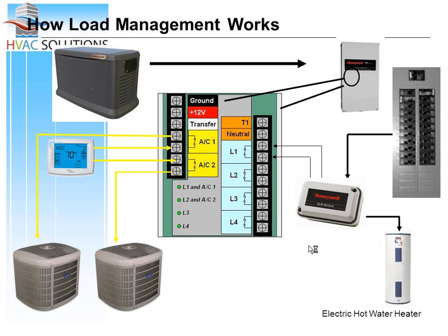So in that case, we wouldn't shed the well pump, even though it's a 240-volt load. We'd leave that on the customer circuit breaker panel without shedding it. The penalty is your generator has to be sized properly, meaning big enough to handle everything on that circuit breaker panel that you're not shedding. If you shed it, you can take that off the sizing. If you don't shed it, the generator has to be big enough to handle it.